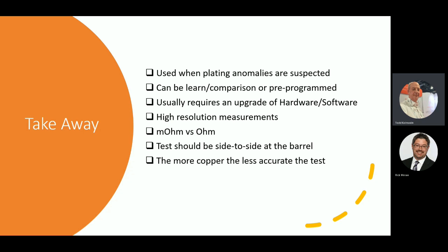When you review the reports and the master, you can make some adjustments. The more copper you have between the measurements, the higher that value is going to be, and you can have a possibility of a little loss of accuracy. You want to be as close as you can from your force and sense probes to get as accurate as possible.